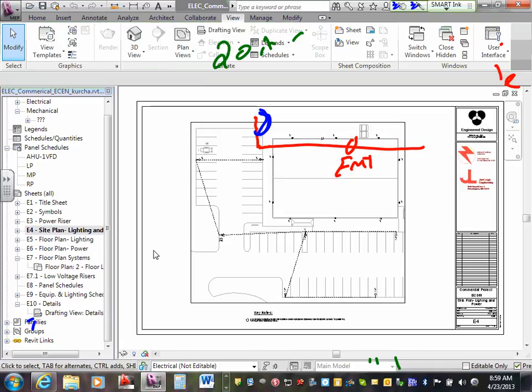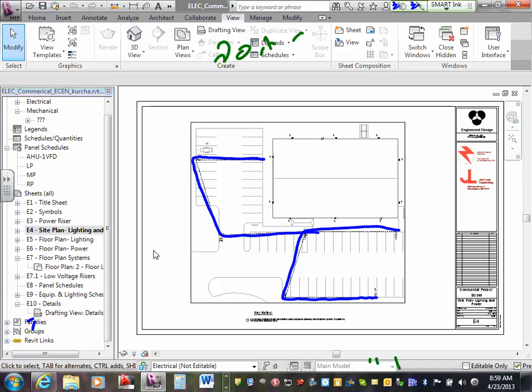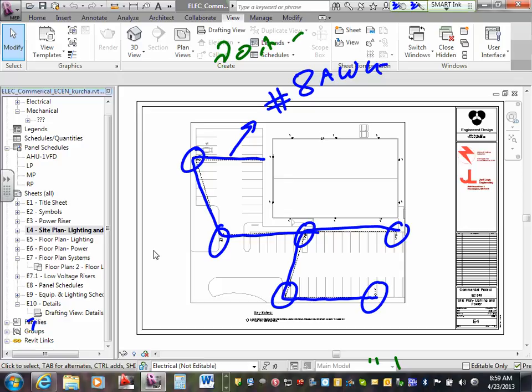When you go to the site, here's what my expectation is from you. I think we use PVC. So we're going to take these off as PVC. We're going to measure them. That's a piece of cake, all the way PVC. There are poles. You are going to account for the poles, installing your lighting poles here. The conductors I would like you to use are not smaller than number 8 AWG. I don't know how many circuits you need. Most of you did one circuit, so that would be 3 conductors, number 8. If we're using PVC, use 3/4 of an inch PVC schedule 40.